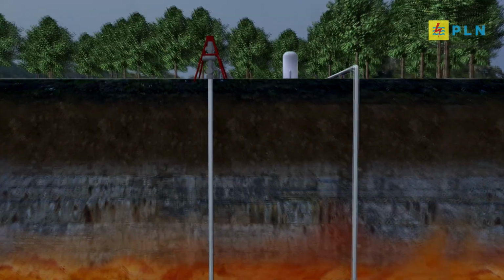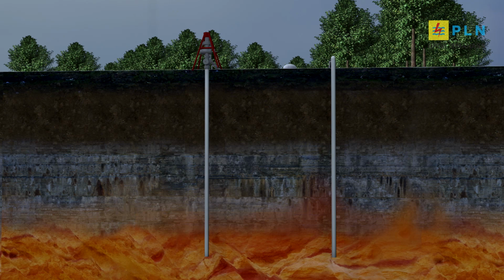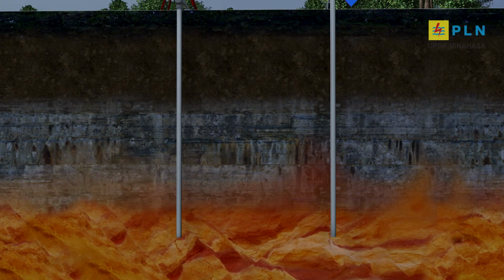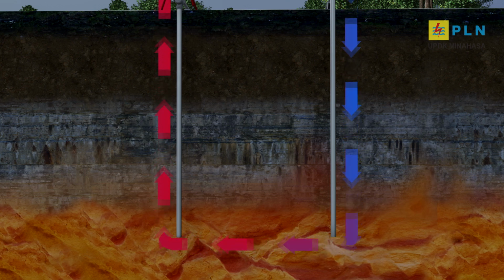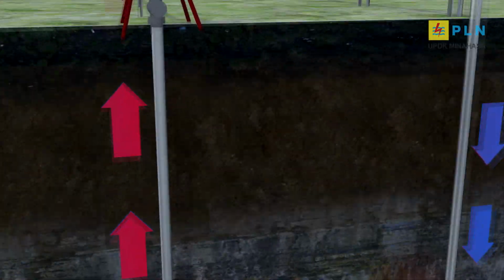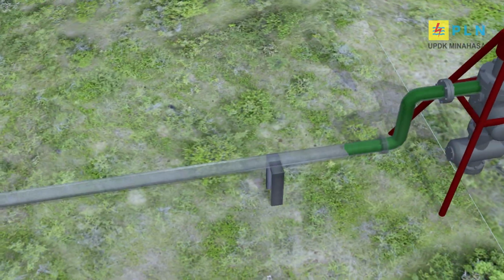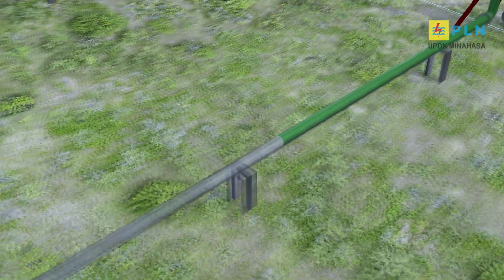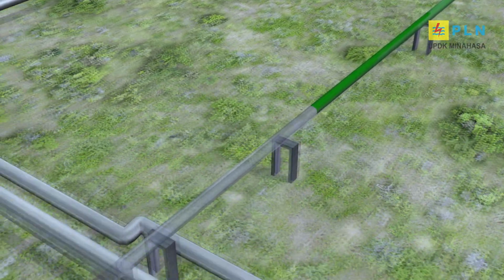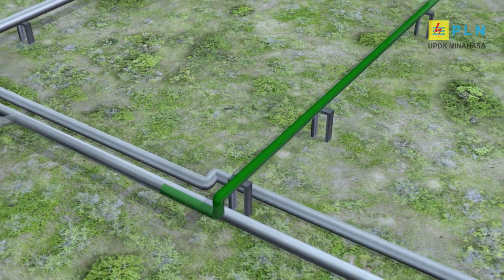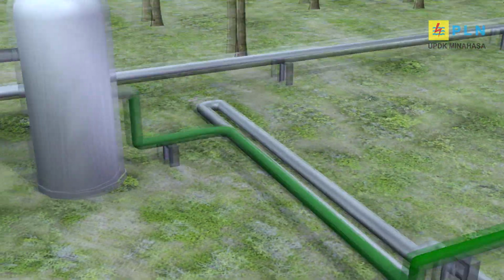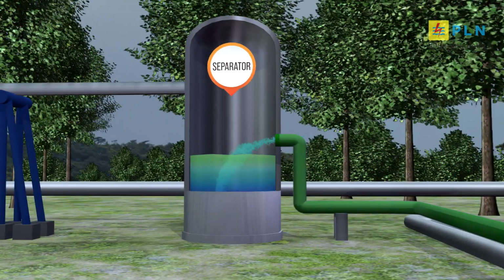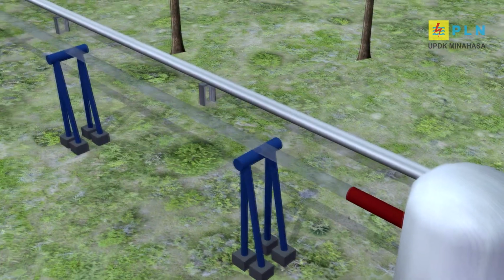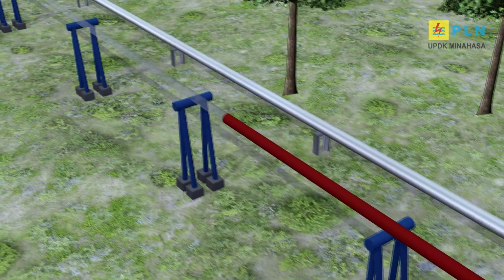Geothermal energy from PLTP Lahendong is obtained from the production wells or Pertamina Geothermal Energy (PGE) steam field, which is produced from the earth reservoir with a depth of about 3,000 feet to 10,000 feet from the Earth's surface. Steam obtained from the bowels of the Earth will naturally rise due to the high pressure in the reservoir.